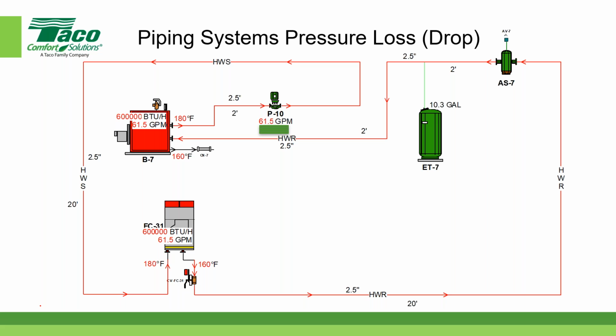And here's a great one. You've done this presentation a few times, and this is the first time someone's asked this: how does open piping, like a condenser water calculation, change, or does it remain the same? So if you're doing a cooling tower and it's open, how does the pressure drop calculation change, if at all? Well, that's a great question.